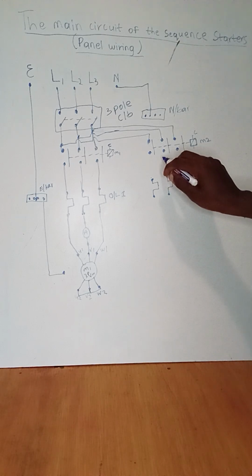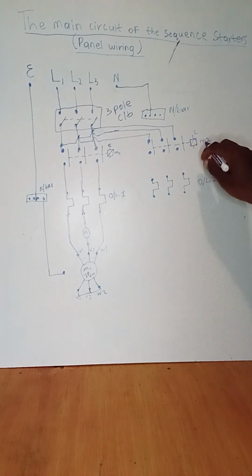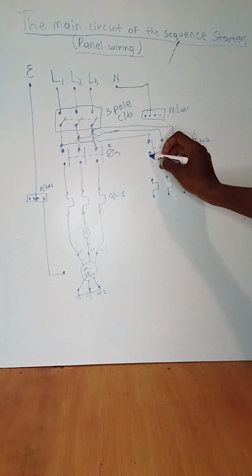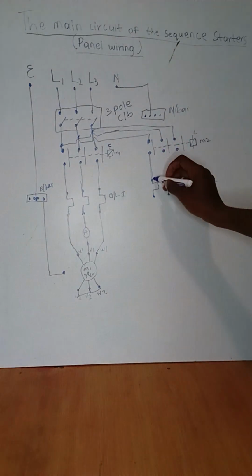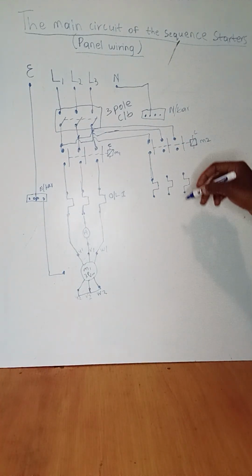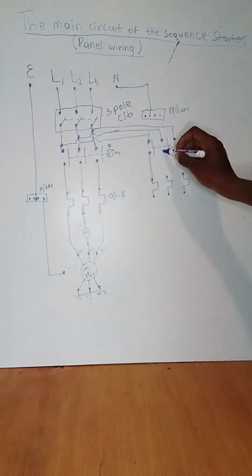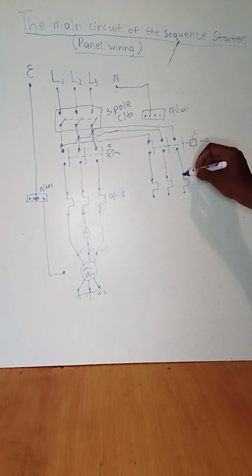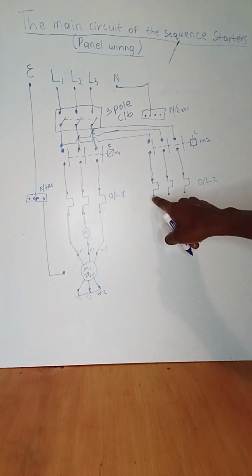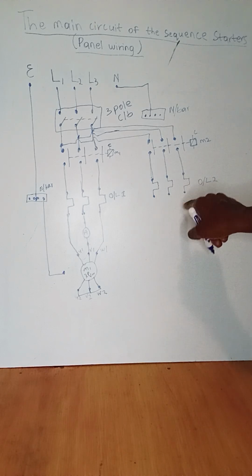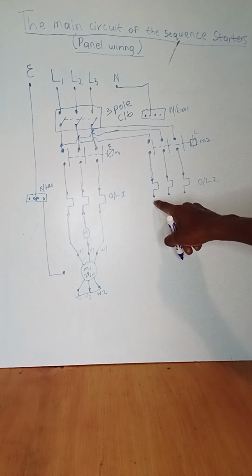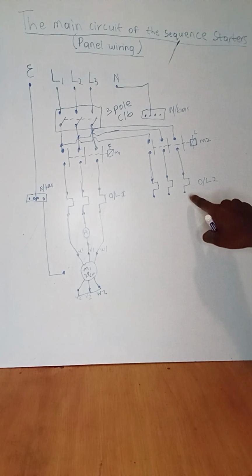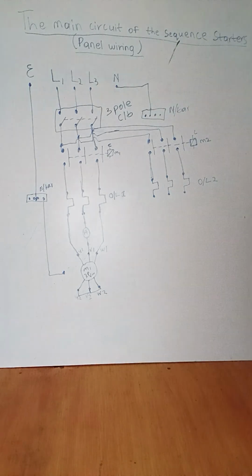Right, so from the bottom points of the contactor of motor 2, line 1, which is the first point, its output will be connected to line 1 of the overload relay 2, and then line 2, the second point, line 3, the third point, and then the outputs of the overload, which is the bottom points, will be connected. Life 1 will be connected to U1, line 2 to the ammeter, line 3 to W1.